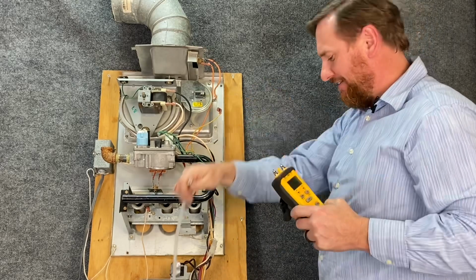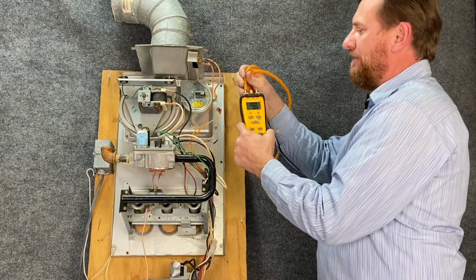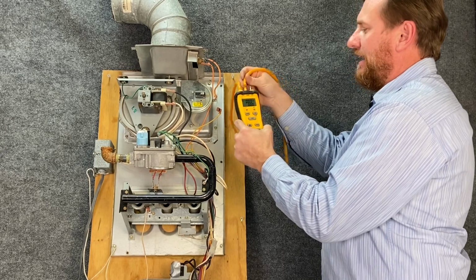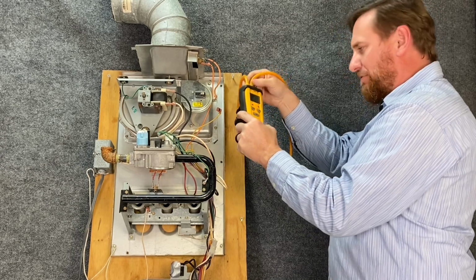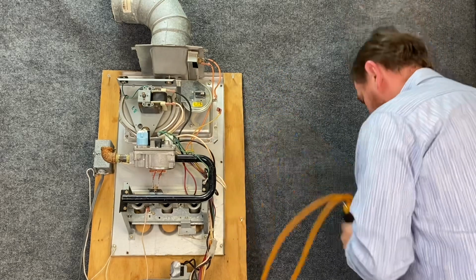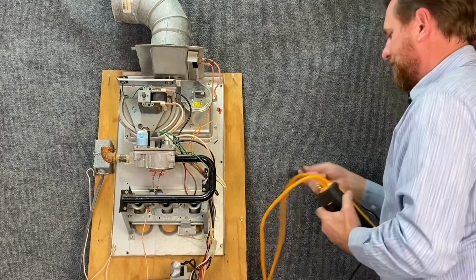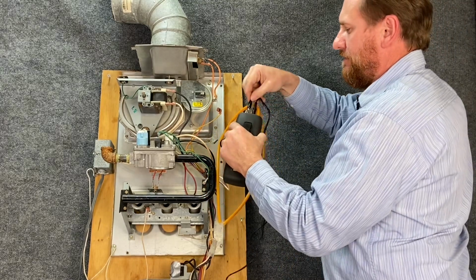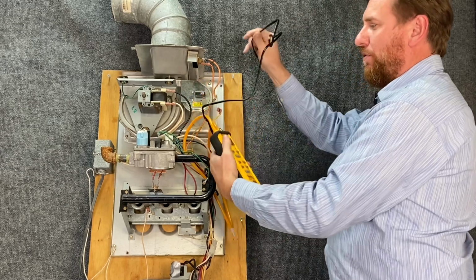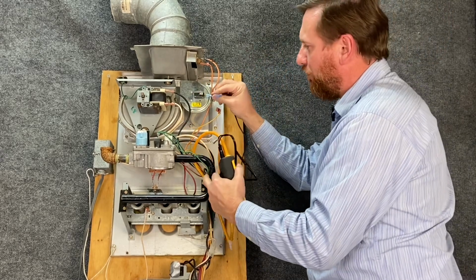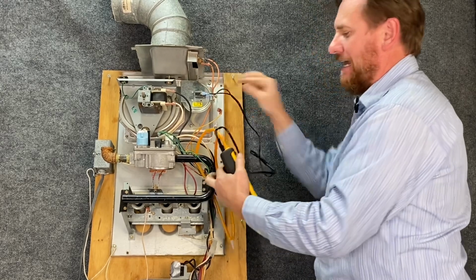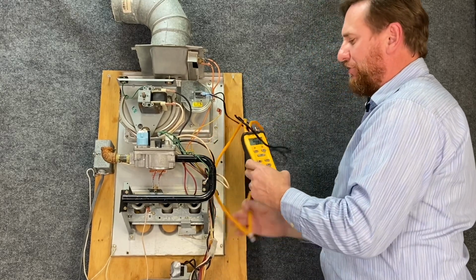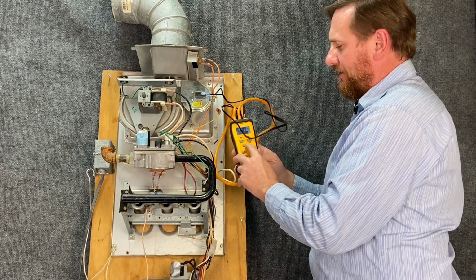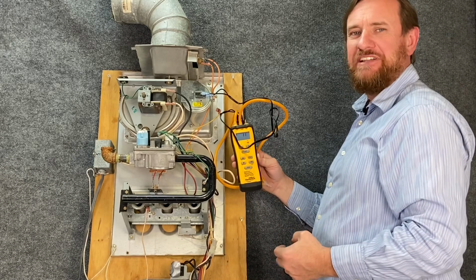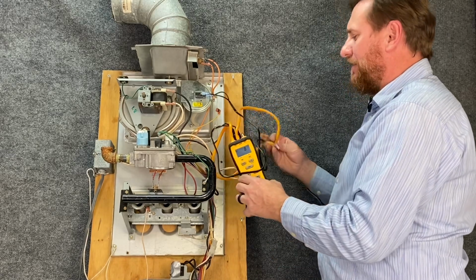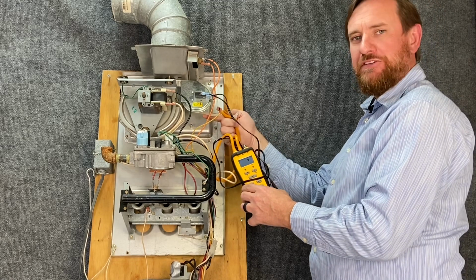I'm going to take this hose and the T off. We're going to put these adapters on. I put one hose on pressure port 1 and one hose on the pump. Then we're going to put an electrical connector adapter on the very end. This cord just has 2 plugs. We plug one into one side of our pressure switch and one into the other side. Now I'm going to turn the pump on for test mode. So I press test. It's going to do a 13-second countdown. At the end of that countdown, I'm going to hook up the T to my vacuum pressure switch.